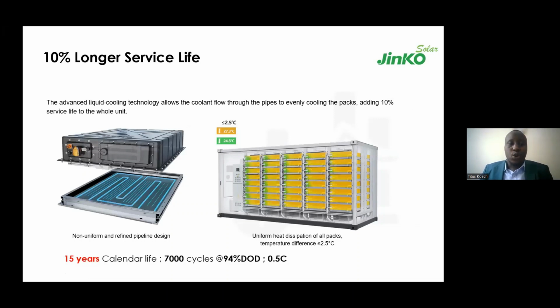And because, like I did mention, there is optimized temperature control, the temperature difference across the whole container, from the highest temperature to the lowest, is under 2.5 degrees Celsius. This uniform heat distribution leads to an increased service life of more than 10%. That's why we are able to guarantee 15 years calendar life, or 7,000 cycles at 90% DOD and 0.5 C. So we can do 15 years or 7,000 cycles, whichever comes first.